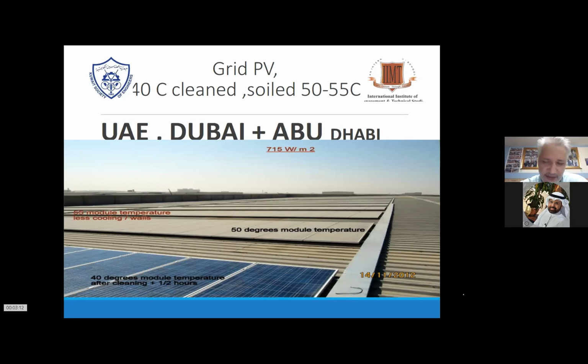That is because, like I said, you have to check the MPPT. The MPPT of the modules and the MPPT of the inverter have to be matched somehow. If the inverter or the modules are the issue, that's where you go in with an IV measurement, with a Seaward or a Benning or whatever device you've got, even a voltmeter, you can see the string voltage. And if you measure your strings, you can see that the voltage of the modules is already derating.